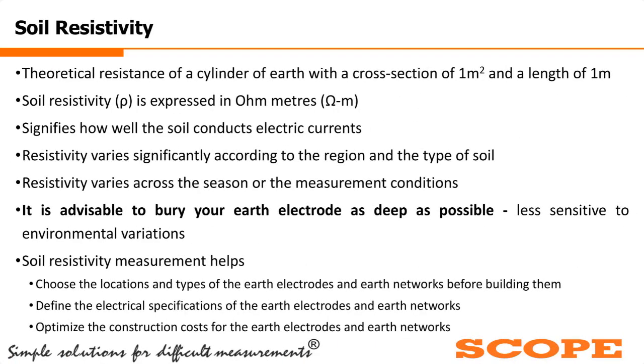Next one, now what is soil resistivity? Soil resistivity is nothing but a resistance. Let us consider an earth cylinder with a cross-section area of 1 square meter and a length of 1 meter. For that particular cylinder, what is the resistance available? This resistance value is called soil resistivity, and it is expressed in ohm meters and denoted by the symbol rho. So what does soil resistivity define? It defines how well the soil can conduct electrical currents when it is connected to any electrical equipment.